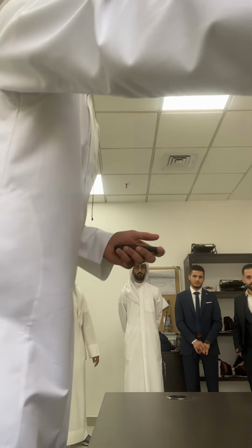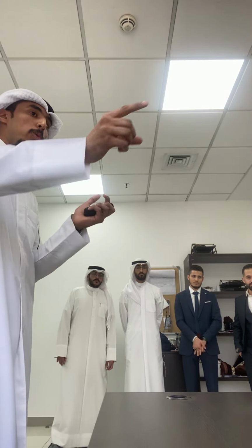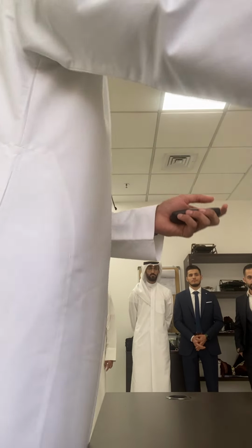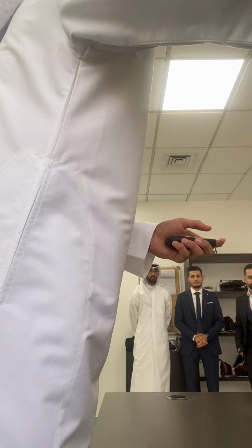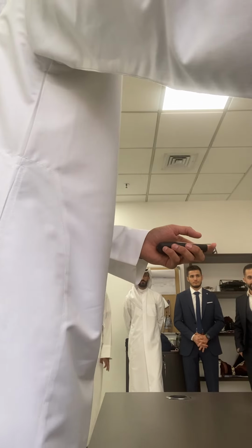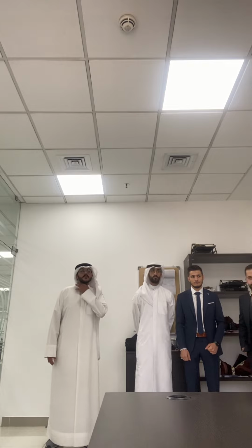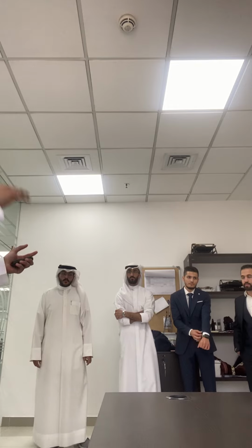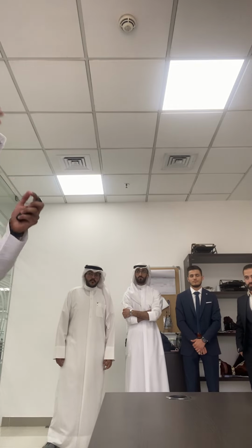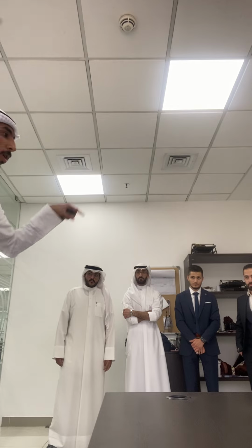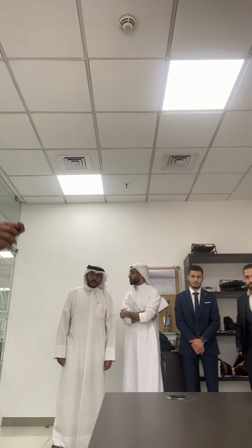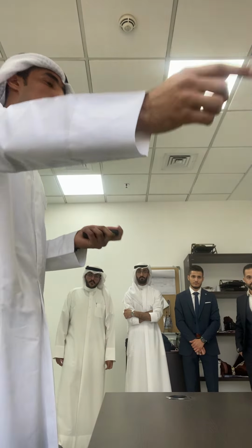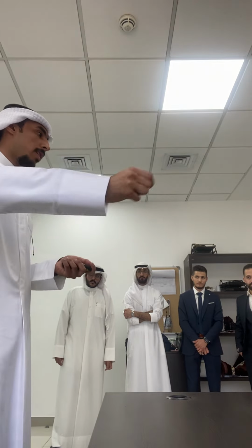We took showroom number 4 as an example to compare the hand calculation and the HAP analysis. We saw that there's a small difference between them. In the hand calculation, we found that the total equals 11.6 kilowatts, and in the HAP result it's 13.9. This is the total heat for the room, external and internal. Because for the showroom there's no unconditioned area, all the space around showroom number 4 is conditioned. So there's a small difference. This is because of some human mistake in the hand calculation.